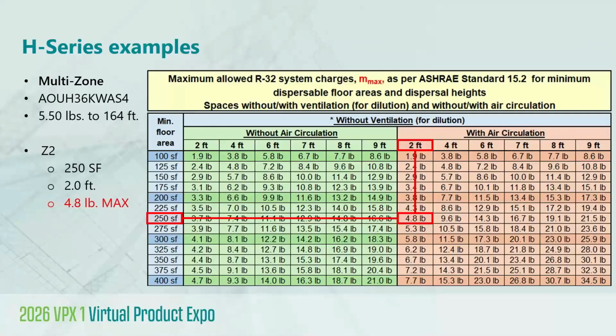So referencing our 15.2 cheat sheet, and as we just mentioned, since the floor-mounted unit includes the LDS to initiate circulation, we can reference the orange tables on the right, that is with air circulation that you see. And in doing so, you'll note that when you intersect the dispersal area, the row going across of 250 square feet, at the dispersal height column of 2 feet, we see the maximum allowed system charge is 4.8 pounds, with the first level of mitigation, again, that being air circulation.